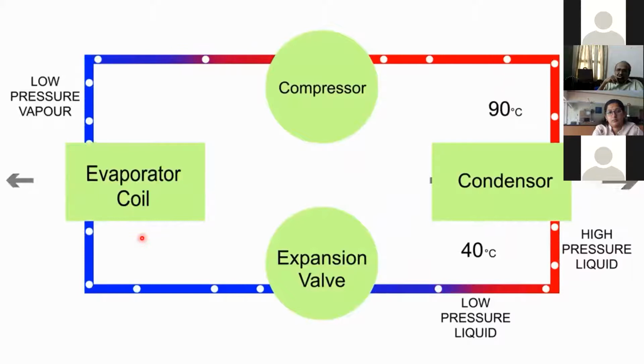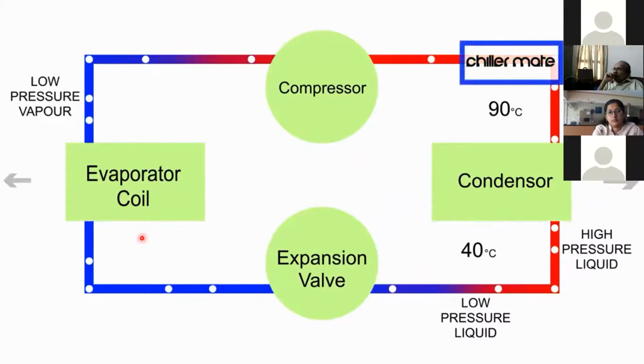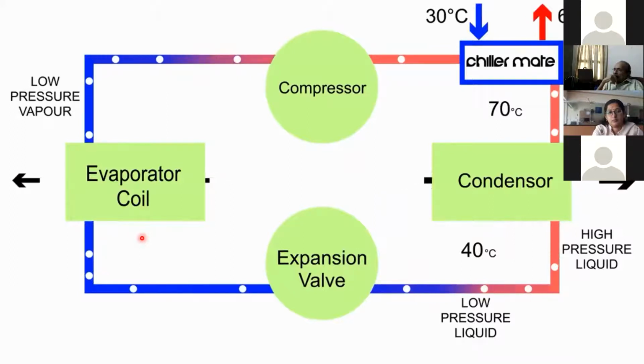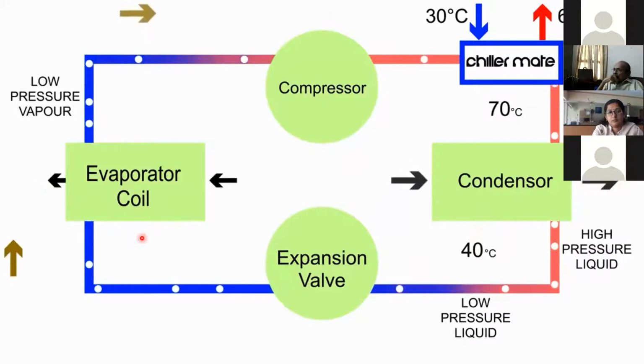So, how does it work? If you look carefully at the refrigeration system, in every cycle, the compressor is generating hot refrigerant at high pressure, and the condenser is rejecting this heat every single cycle. ChillerMate is a unique patented heat recovery system which sits between the compressor and condenser and recovers this wasted heat and converts it to hot water. So you both cool down the refrigerant while generating zero-cost hot water at the same time. This hot water can be used in other processes and can offset your fuel usage significantly, generating savings.